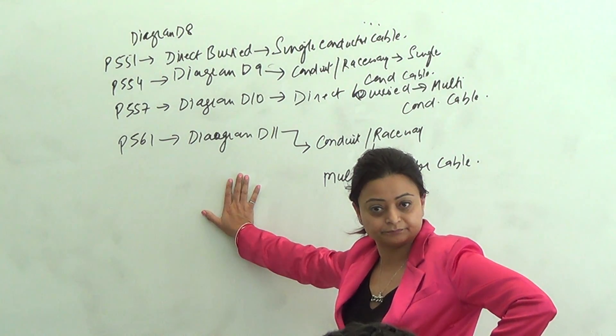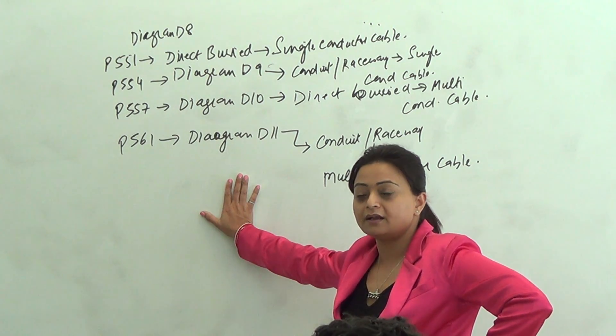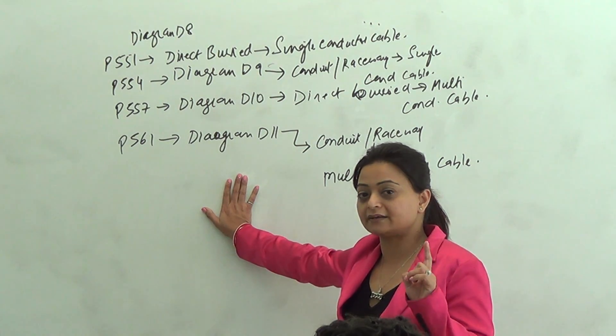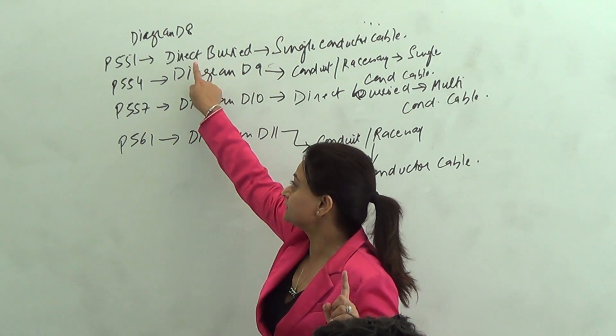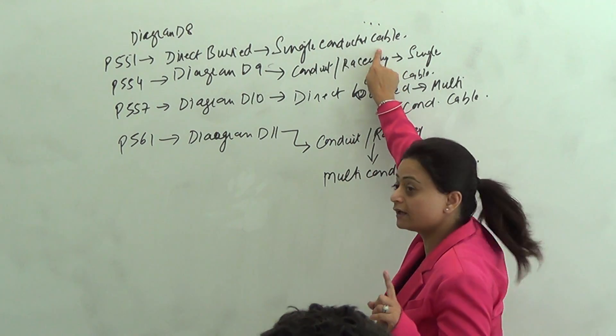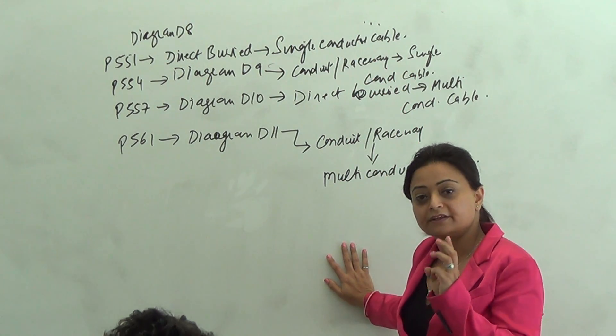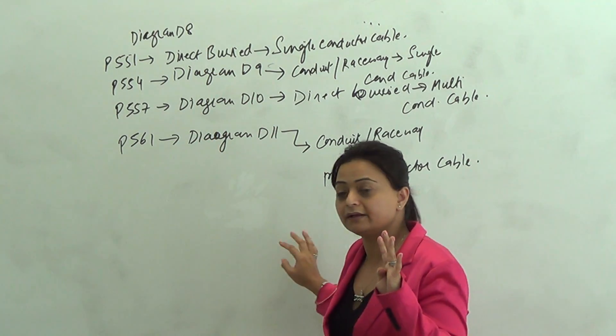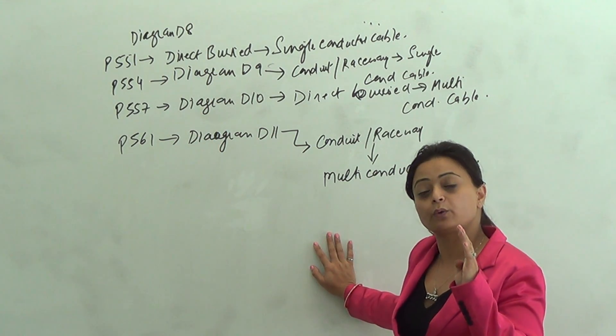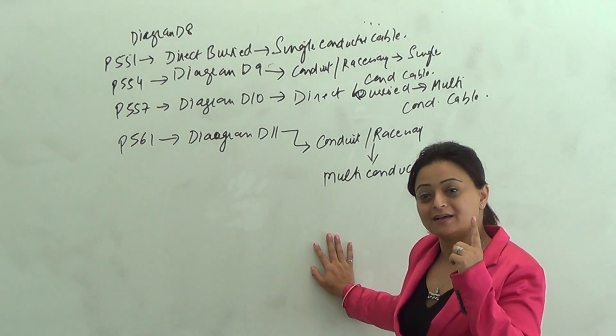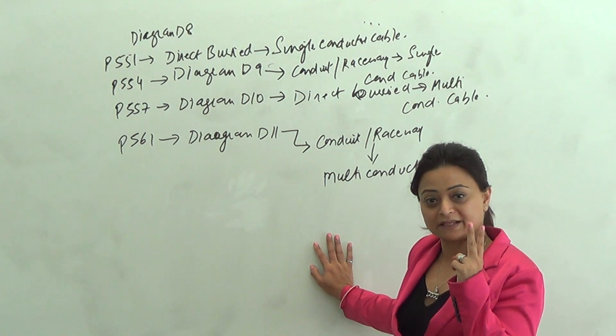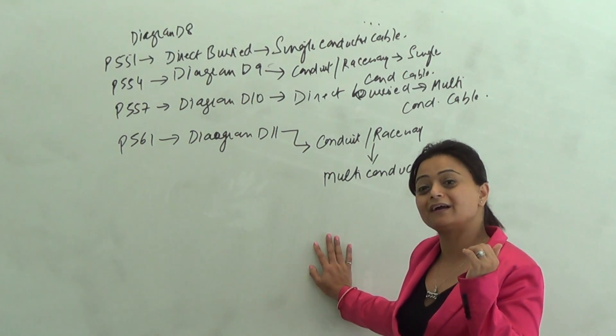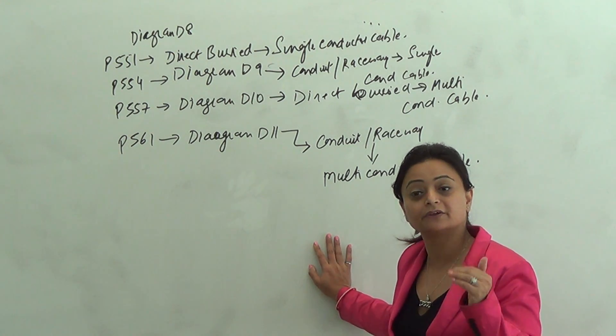What size wire would I choose? None of that part of the question said parallel run. But the key words that I just said were conductors are directly buried and they are single conductor cable. These four diagrams, diagram D8 all the way to diagram D11, talk about whether the installation is single conductor cable or multi-conductor cable. It's further subdivided into whether I am installing it without the conduit or with the conduit.